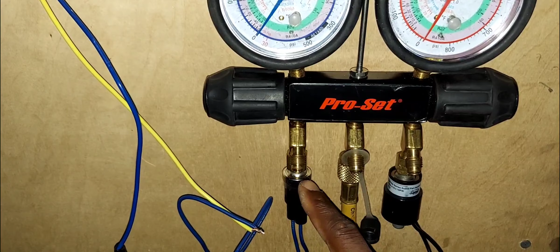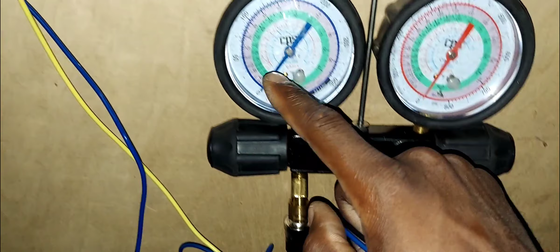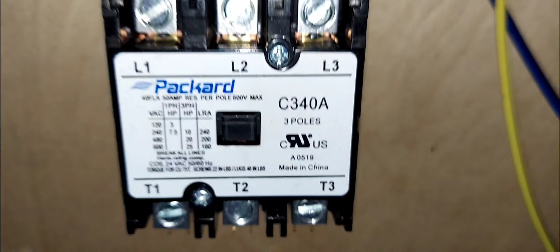Right now, the normally open switch is open, which is a low pressure switch. It's normally open until the pressure is up. This one is rated for 65, so once the pressure goes above 65, it will close. Even though we're calling for cooling, and the system is wired up like a regular system, my compressor contactor is not energized.